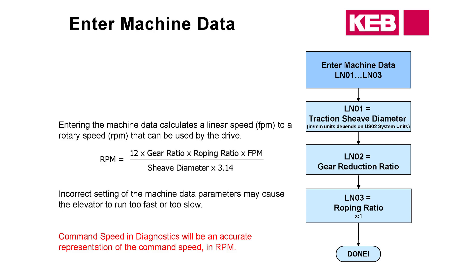We also have an equation you can use if you're wondering whether your motor is rotating at the correct RPM for a given foot-per-minute speed. It's: 12 times the gear ratio times your roping ratio times the speed in feet per minute, divided by the sheave diameter times 3.14. If you don't have a tach, this should tell you pretty closely what your motor should be rotating at for a corresponding foot-per-minute speed.